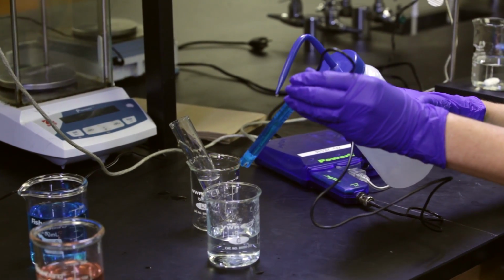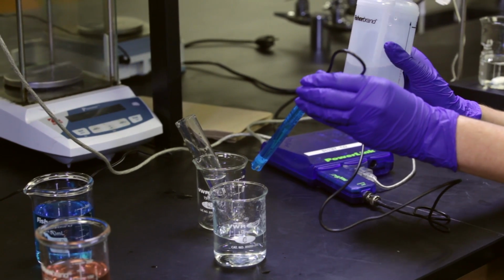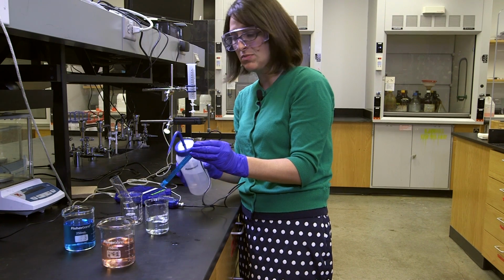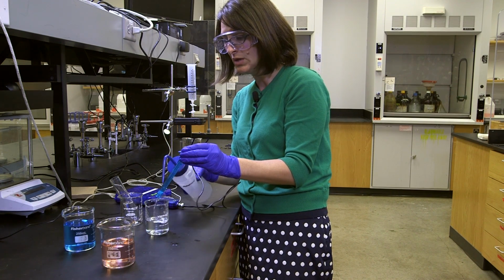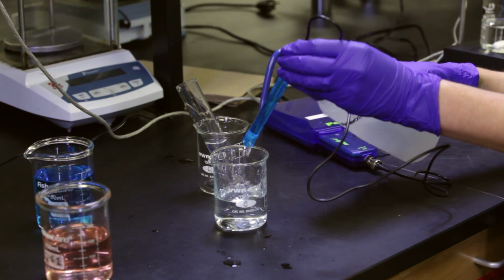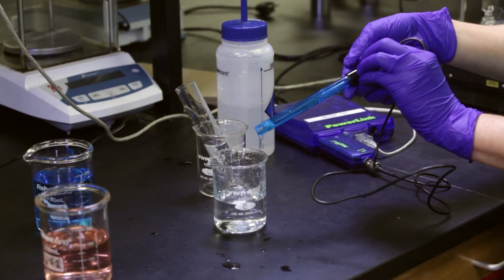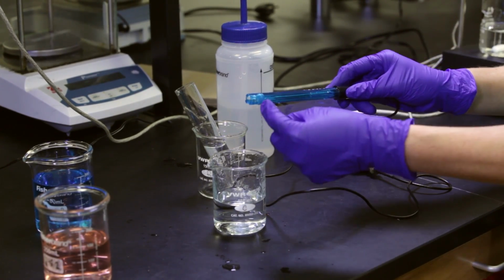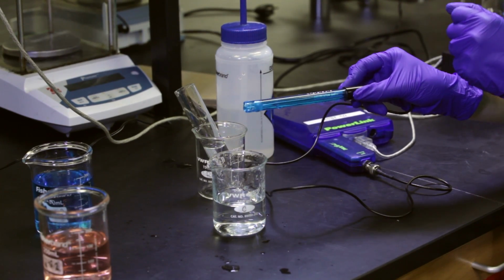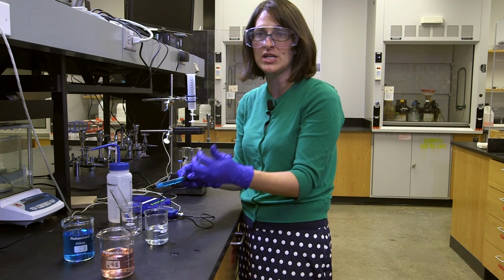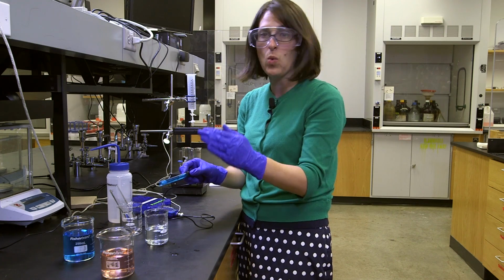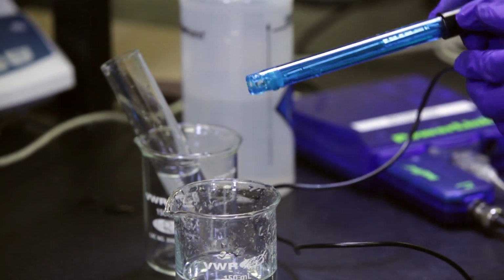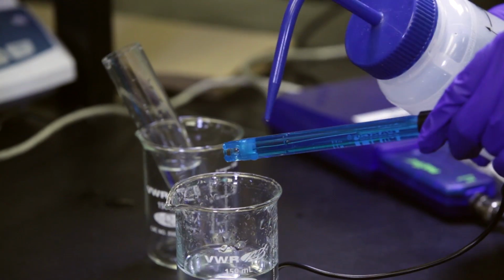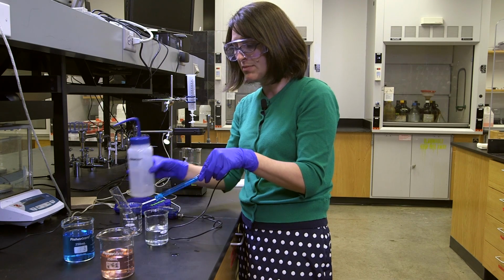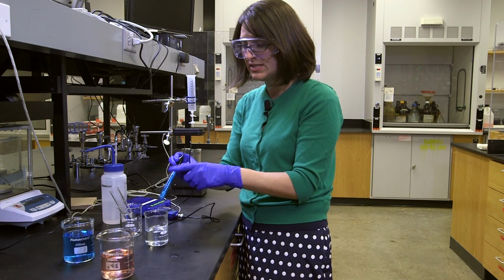So every time I use my pH probe, I'm going to have a squeeze bottle of DI water and an empty beaker to catch the water as I rinse it off. You can see at the base of the probe, it's kind of like a little cage around a glass ball. And it's really important that I don't touch it, I don't stick anything in there, I don't wipe it off with a paper towel. I don't want anything touching that. I'm just going to rinse it off every time I'm changing solutions. So this needs to be in a solution.